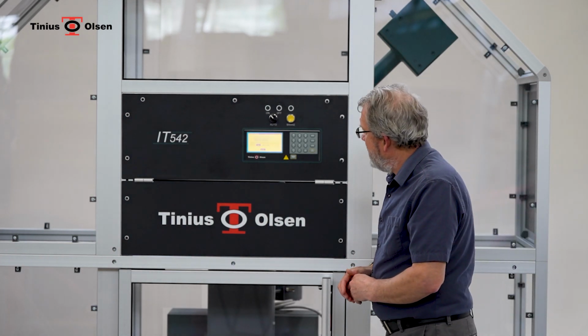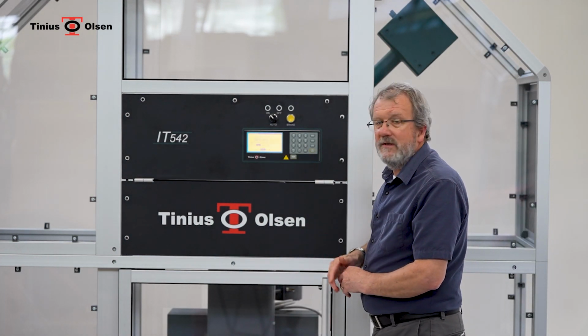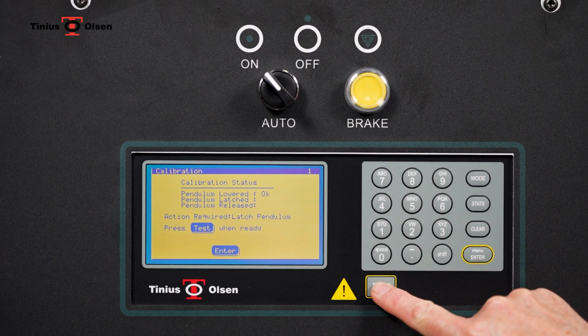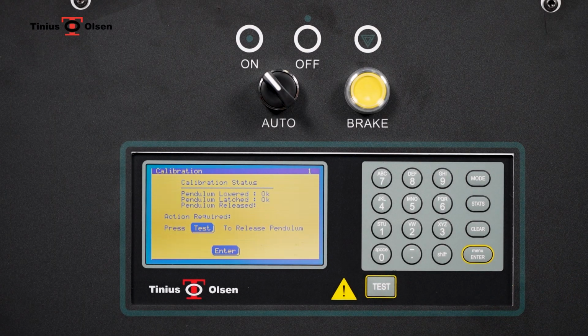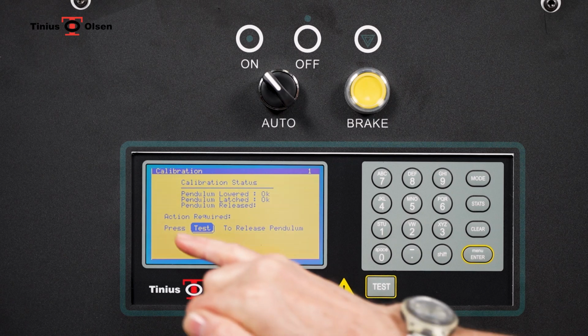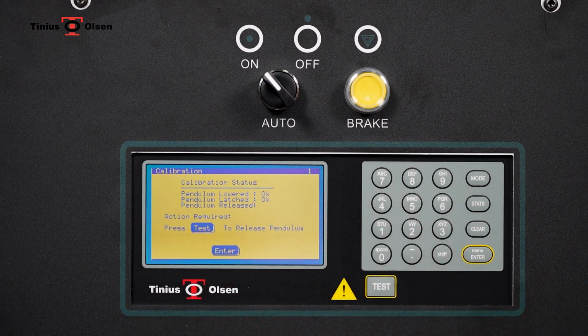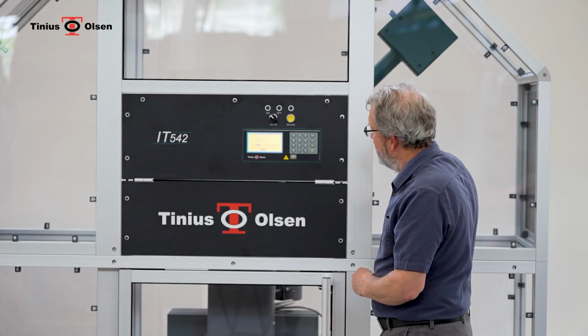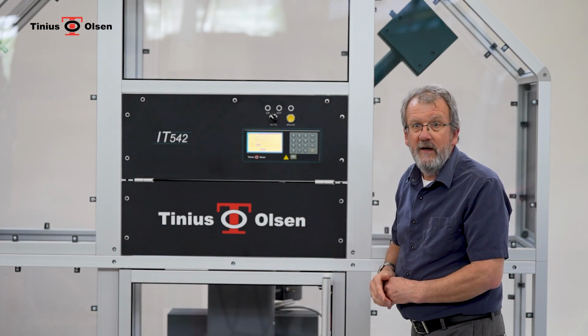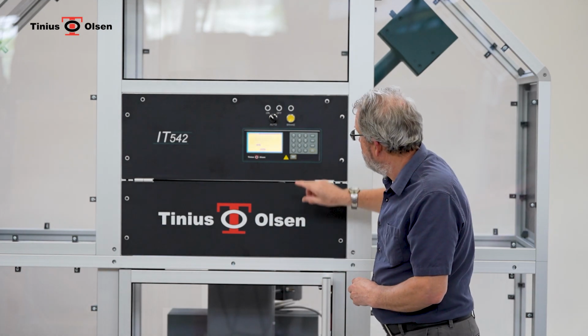Once the pendulum has latched, we are required to press test when ready. Pressing the test button records that value. Action required, press test to release pendulum. At this point, we will press test. It will do a free swing and capture the energy loss on that swing.